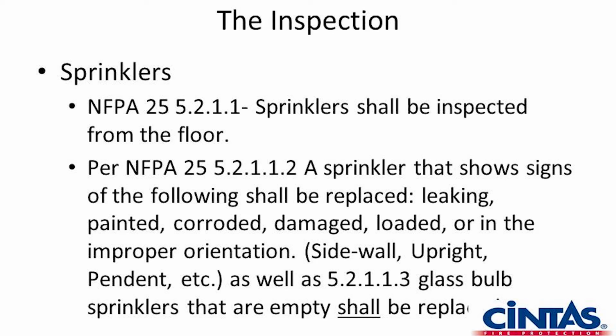So those are two major things with painting. Obviously, if the sprinkler head is damaged, you could have a false trip of the sprinkler, or if the deflector, the round part at the bottom, is damaged, we're not going to get the spray pattern that we're looking for. Different orientations of sprinklers could be sidewall, upright, pendant, and there's even a vertical sidewall. It's a sprinkler head that looks like it's pointed down in a pendant position, but the deflector is turned out, so the water hits and then sprays out sideways from a sprinkler that looks like it's pointed straight down.